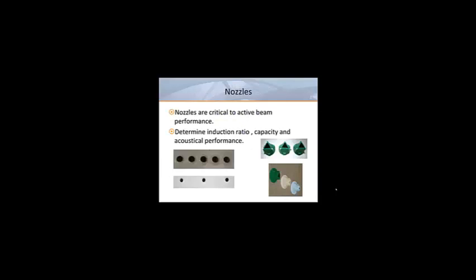The nozzles are absolutely critical to the performance of an active chilled beam. The nozzles must be properly selected to handle the primary air volume and create the induction required to achieve the cooling capacity. Although active beams are usually only available in a few standard lengths, differences in the size, number, and style of nozzle can create major differences in all aspects of beam performance.